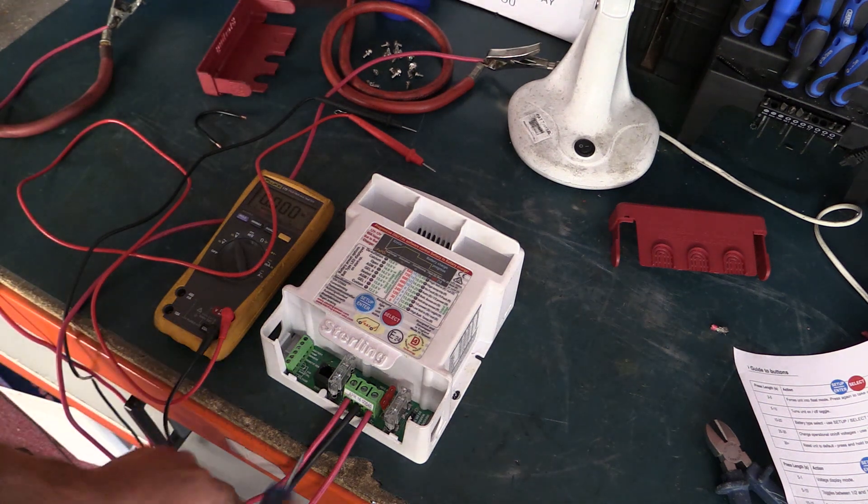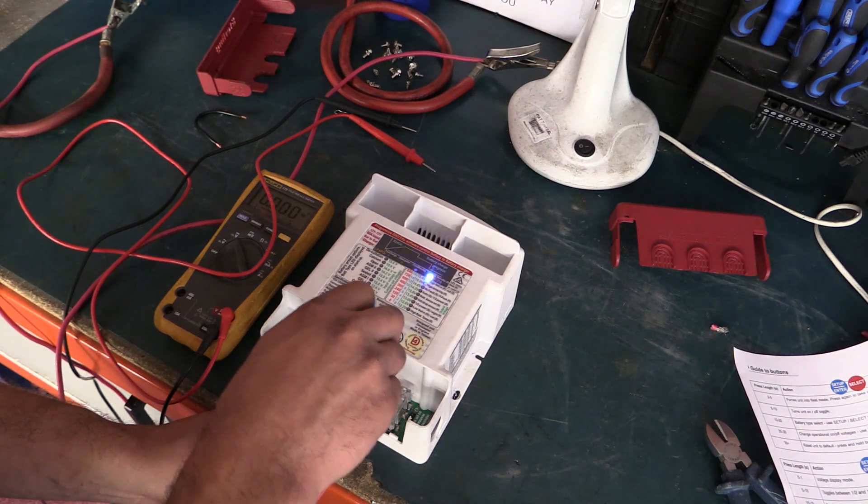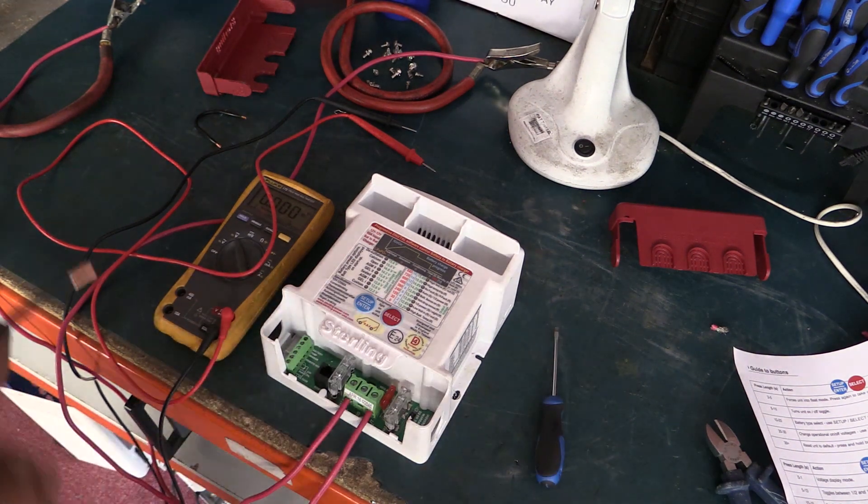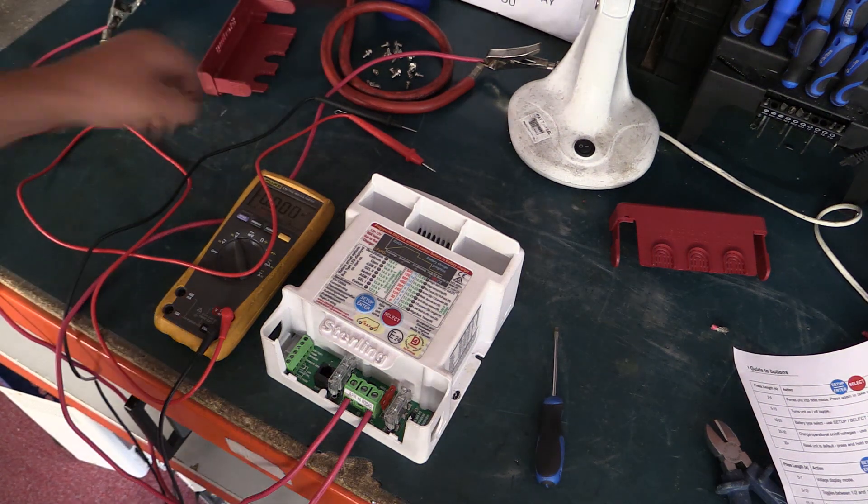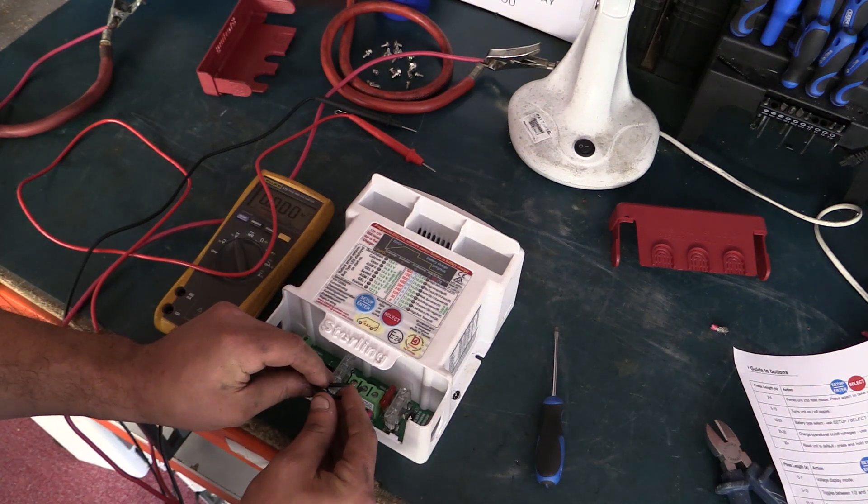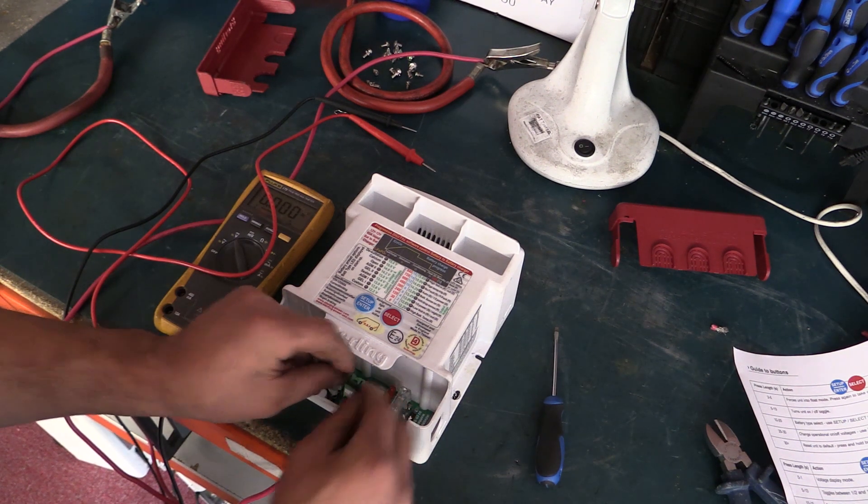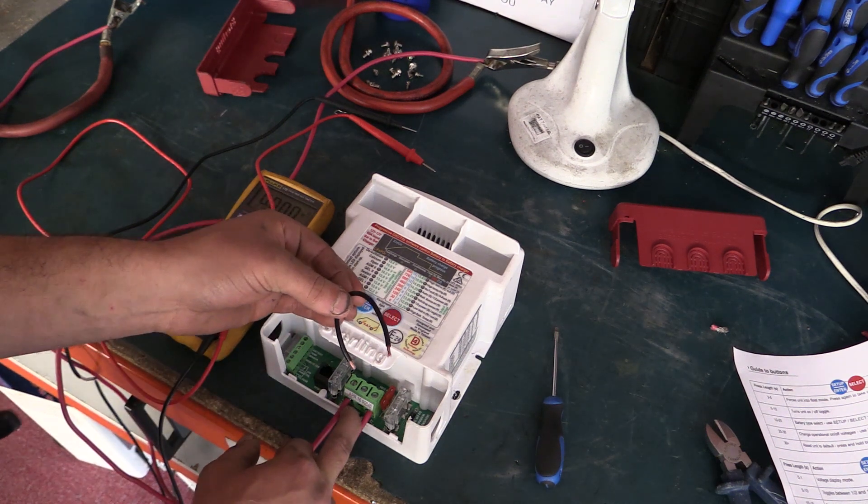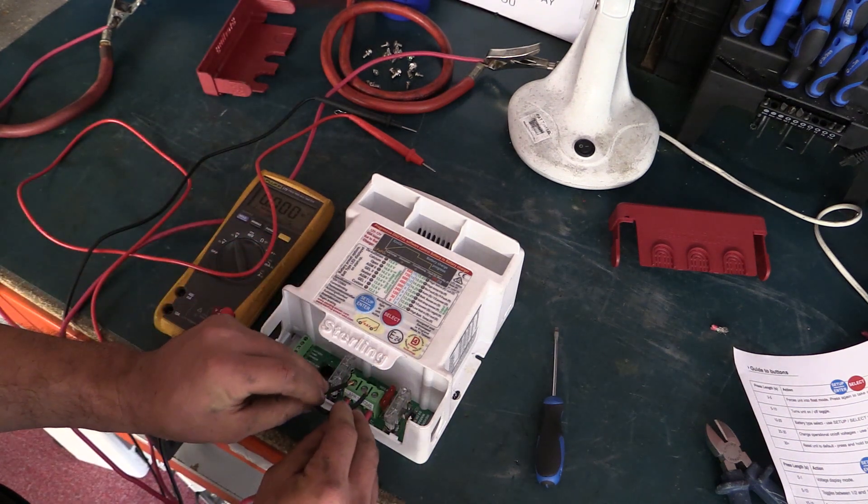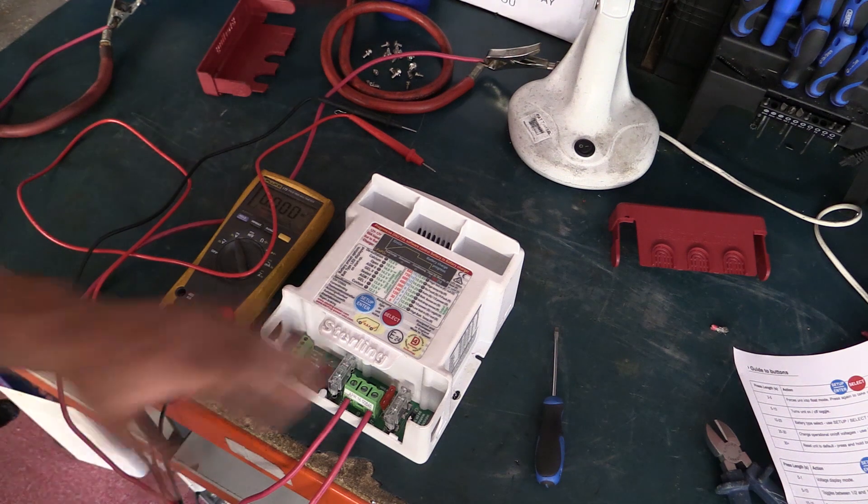We're going to remove the negative. I'm going to put the negative quite far down on the screw so that when we reattach it, it should be a bit easier so the slot should be free to be able to put the negative in. So we've removed the negative. What I'm going to do is use the link wire here, just going to go over the top of these two. You will probably see a spark, which is quite normal. Just as a word of caution, make sure you have definitely removed the negative before you use a link wire, otherwise you'll be shorting your battery out and we don't want that. What we've done is popped this bit of link over between the negative and the input and then a negative on the output. The unit there is completely, all of the capacitance is discharged.